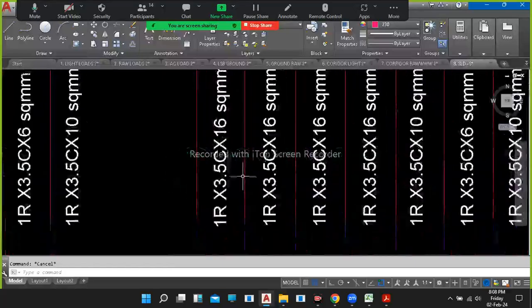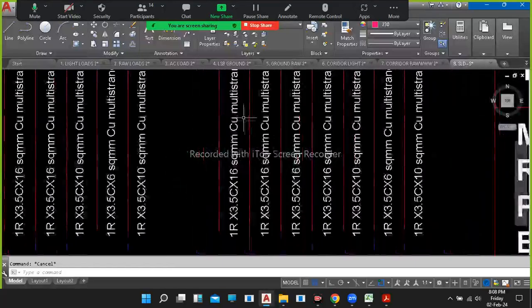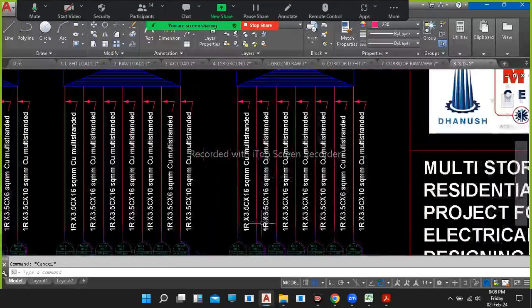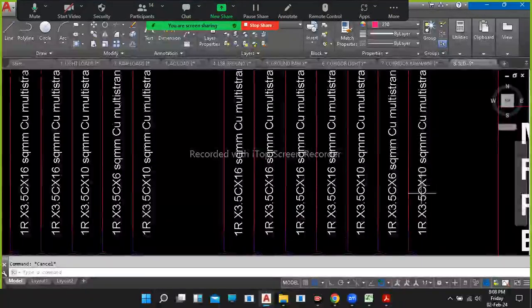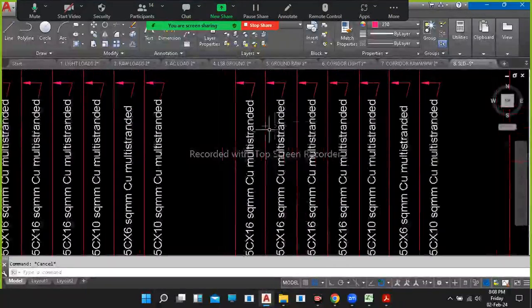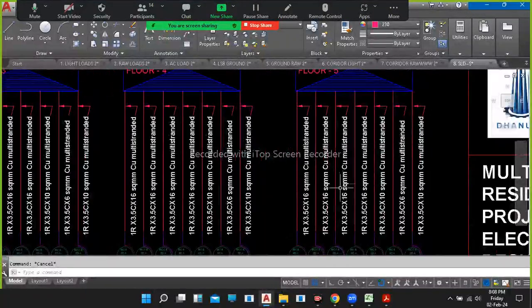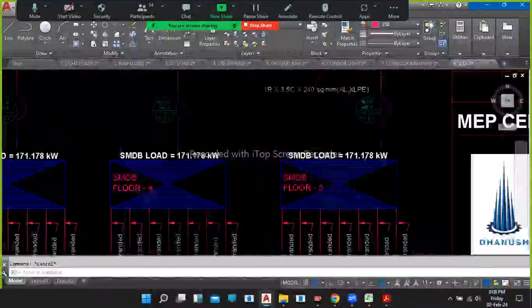And what the cable size is, he got 3.5x16 sq mm. He got 16 square mm. So based upon the load, as per your calculation which was done yesterday, we'll be putting the cable sizes for all the feeders. Adding up all these 5 flats' load, we got the SMDB load.